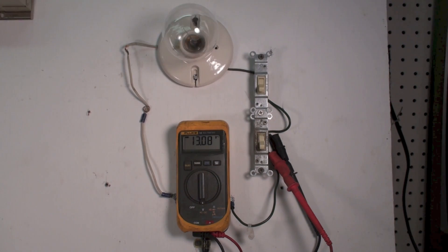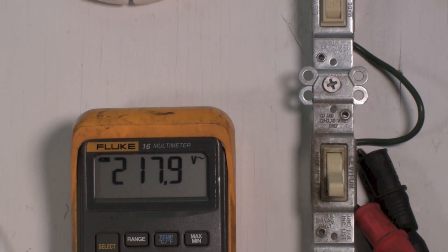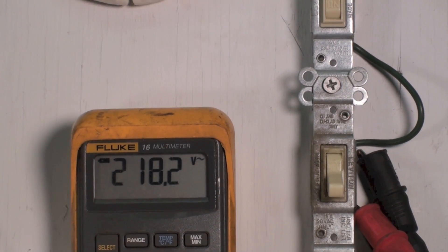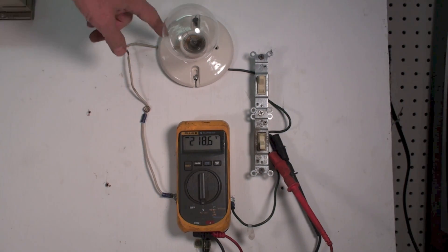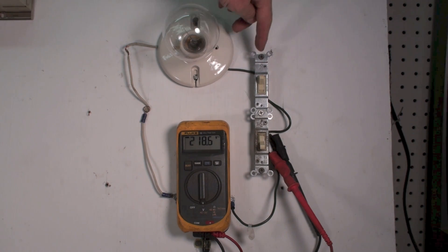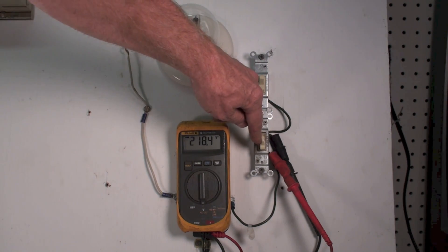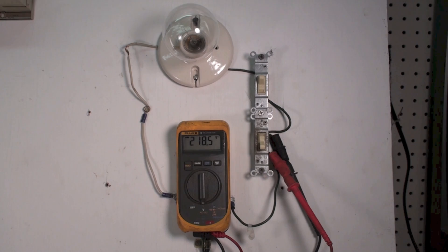Now these are manual switches. They could be pressure switches, limit switches, whatever. Now let's say one of those switches is off and one's on. You can see we're reading line voltage because I have power from here, up through the load, over to the switch which is on. The jumper jumps to the second switch which is off and back to the power. So this is telling me this switch is off, this switch is on, and the load is good.